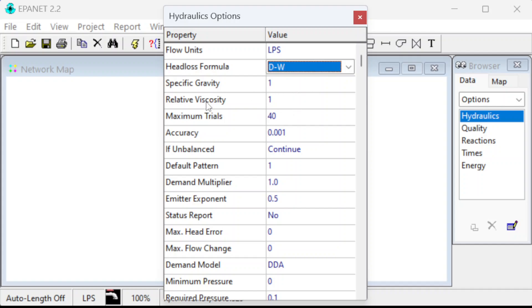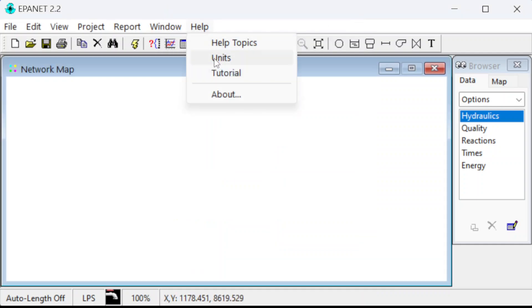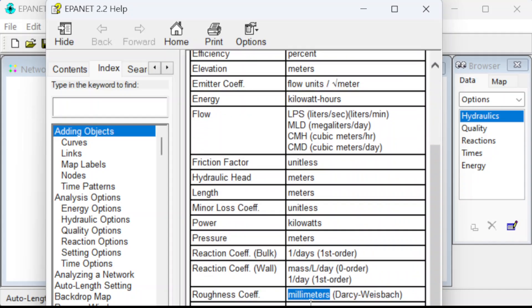A few other options to look at are specific gravity and relative viscosity. EPANET will assume you're at twenty degrees Celsius for these. If you want to use a different value for viscosity at a different temperature, you can put an adjustment factor here — so if you made it 1.1, it would multiply the value at twenty degrees Celsius by 1.1 and use that. So we've got those two things set and now we should be good to put in information. It's generally a good idea to double-check the units. Demand will be in liters per second, pipe diameter needs to be in millimeters, and elevation in meters.